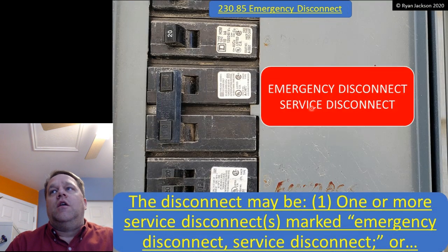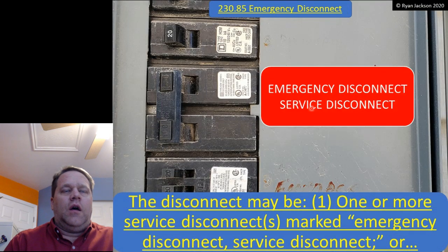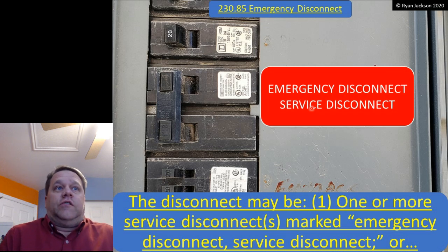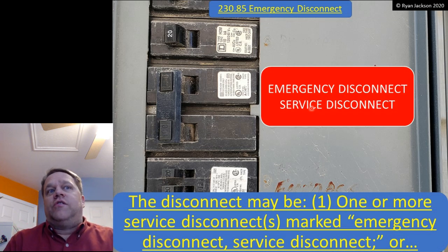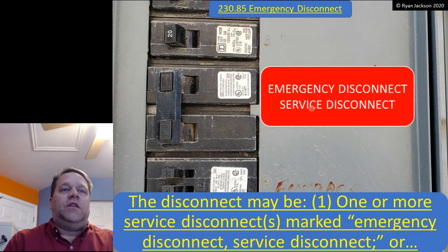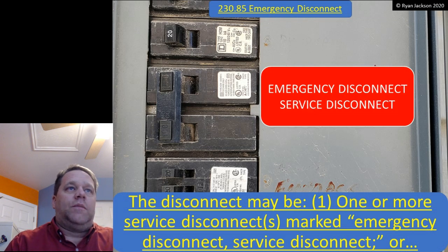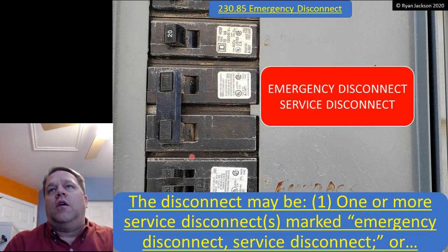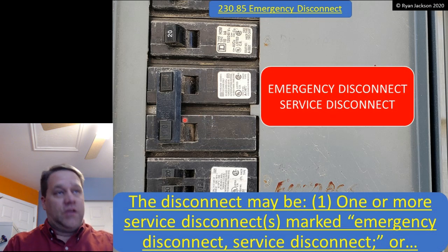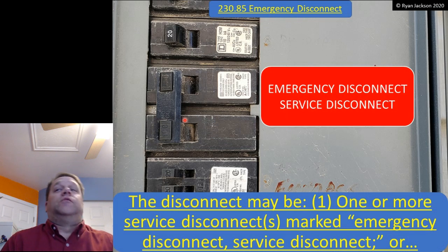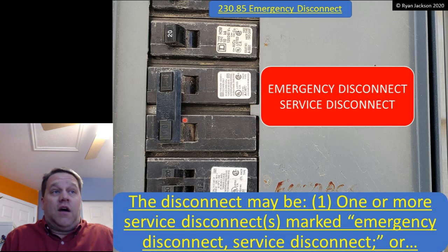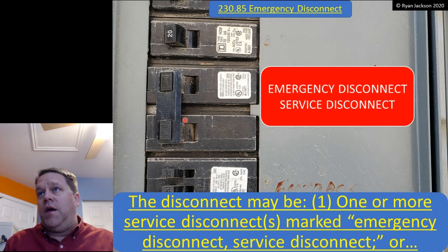The disconnect can be one of, I think, three options, although number one is the one you're going to see. The disconnect can be one or more service disconnects that are marked emergency disconnect, service disconnect. So outside, you walk out to the panel, you've got your two pole 100, you shut it off. Right next to it, you've got the sticker, emergency disconnect, service disconnect. That's it. In my opinion, that's probably going to be the easiest way of satisfying this requirement. This is the method that I see all day, every day around me, and I think it's going to be the method that you start seeing around you.